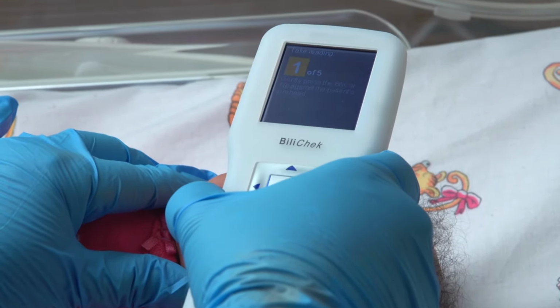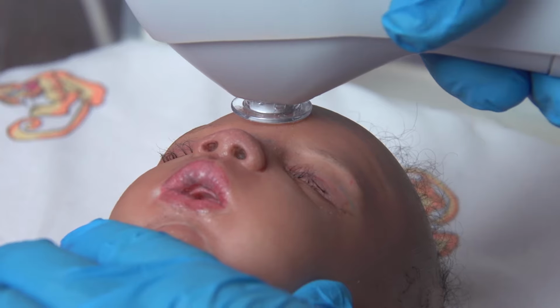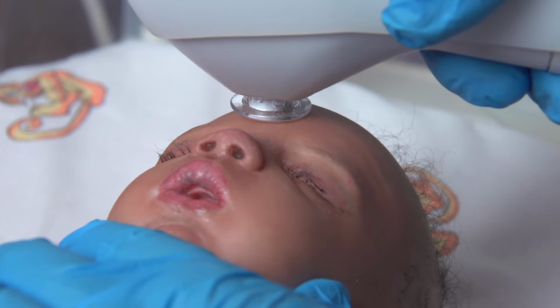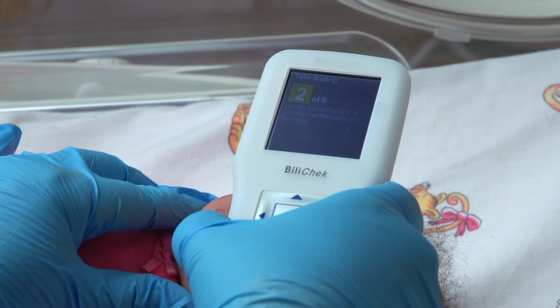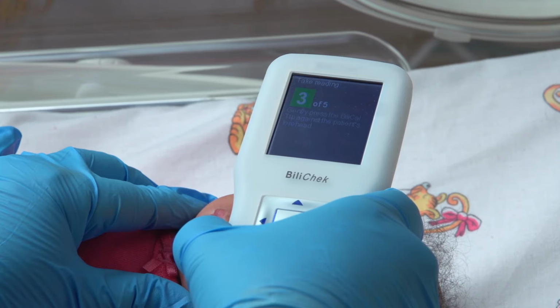While maintaining skin contact with the BiliCal tip, lift the handheld unit slightly from the patient's forehead or sternum and then repeat the process 4 more times. A measurement requires a series of 5 successful readings from the same site.